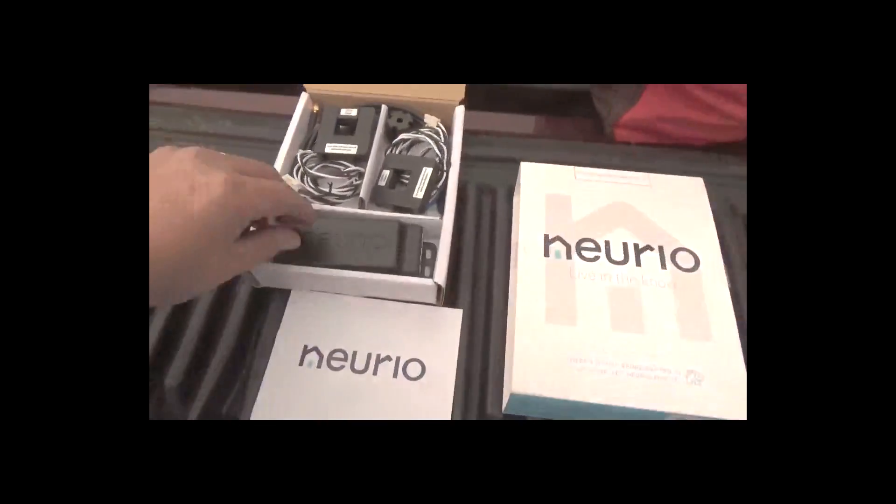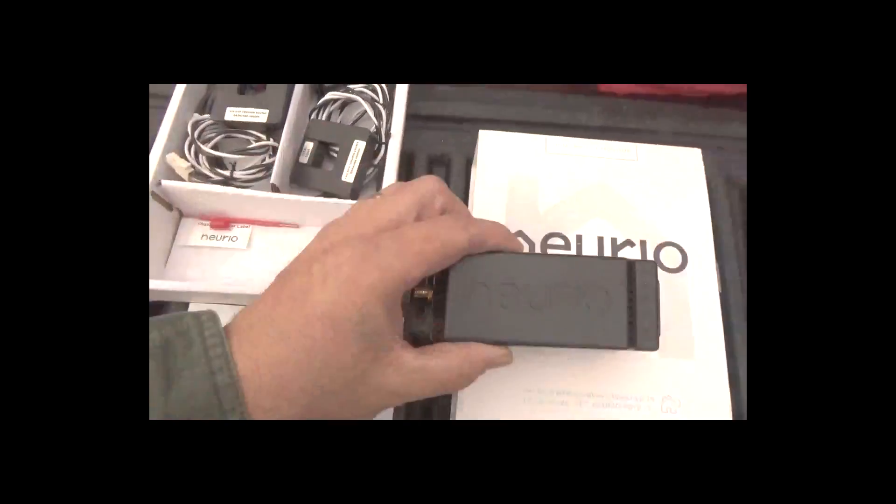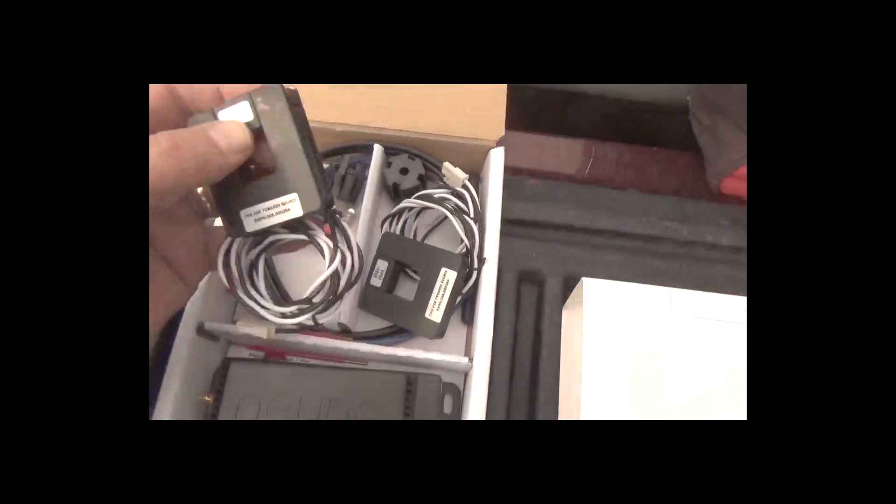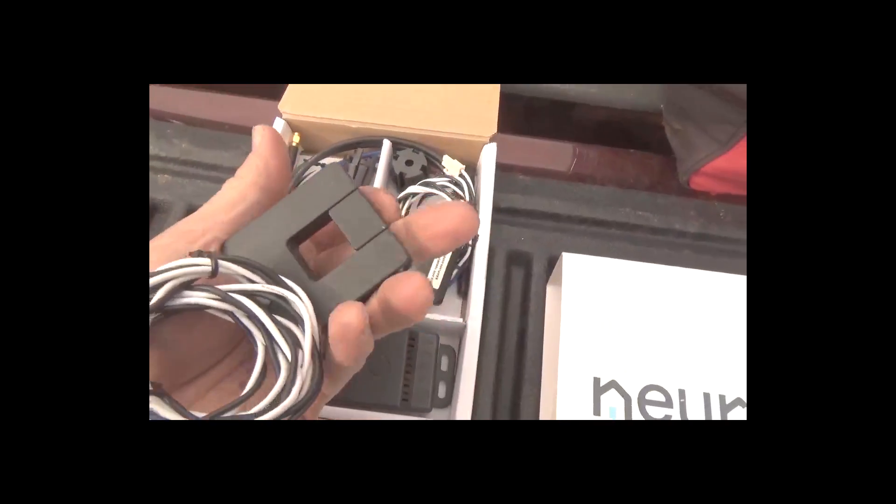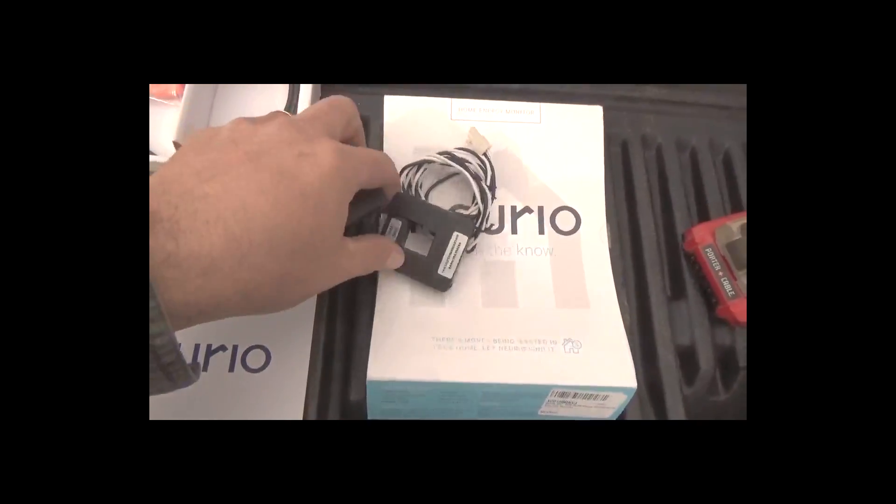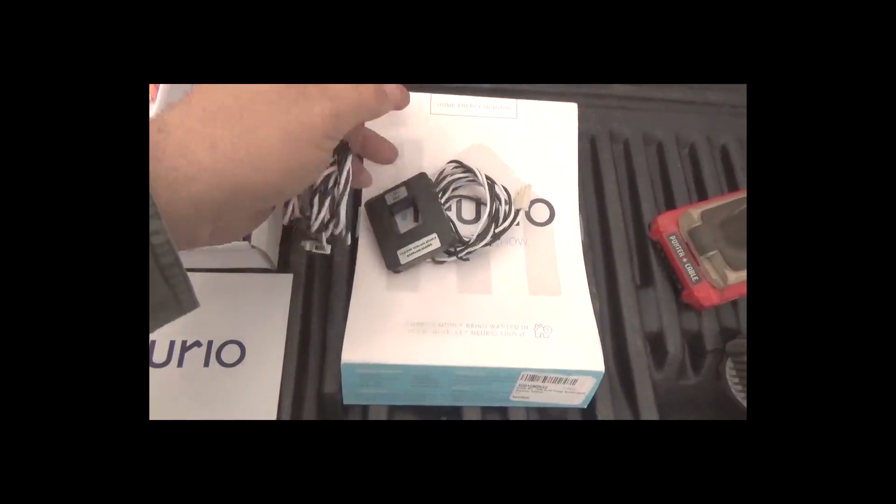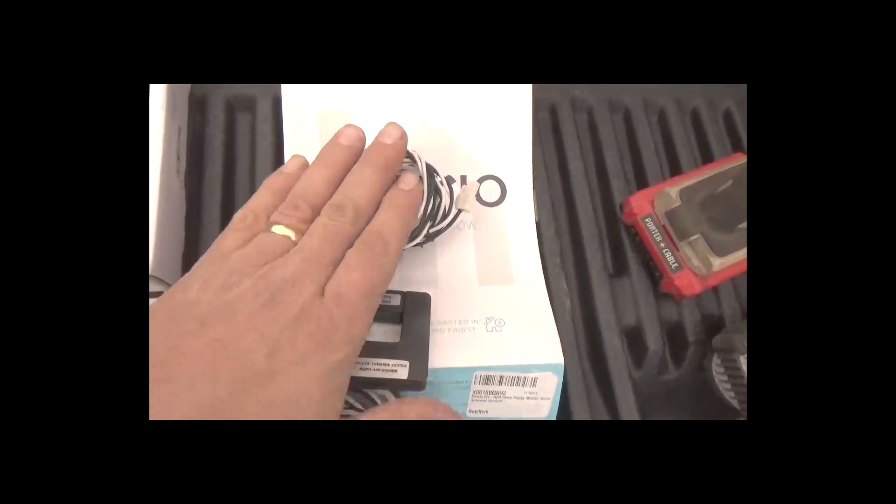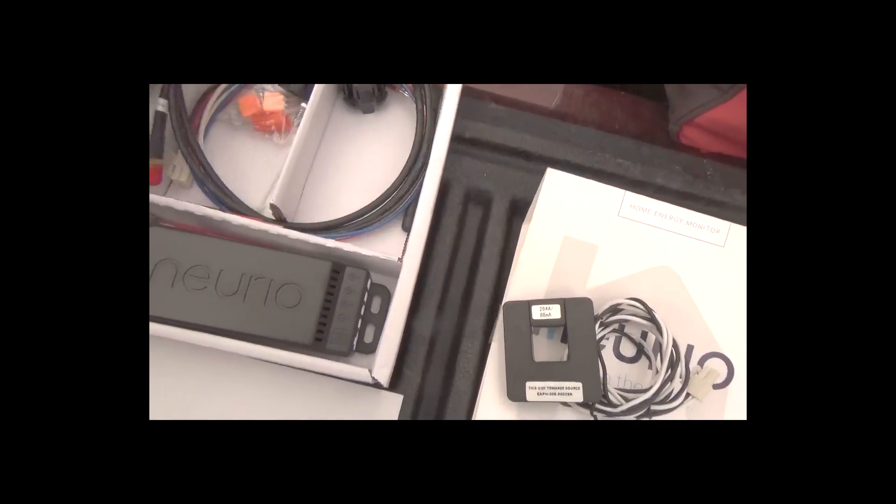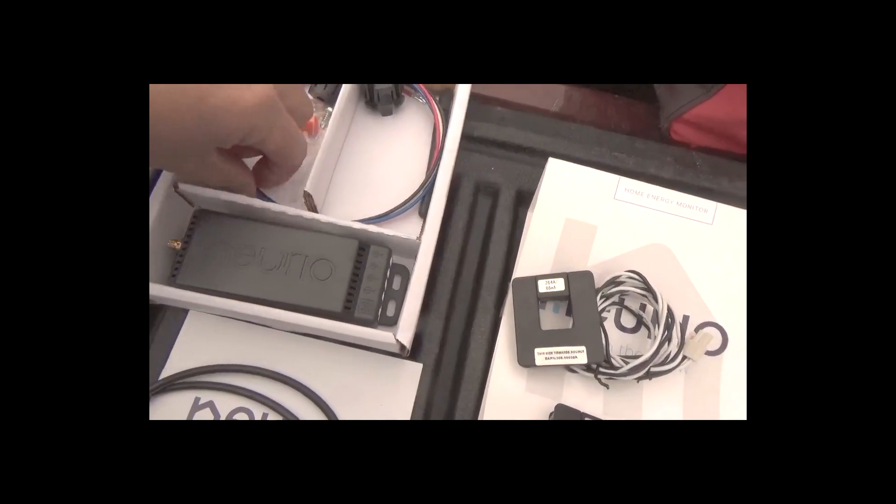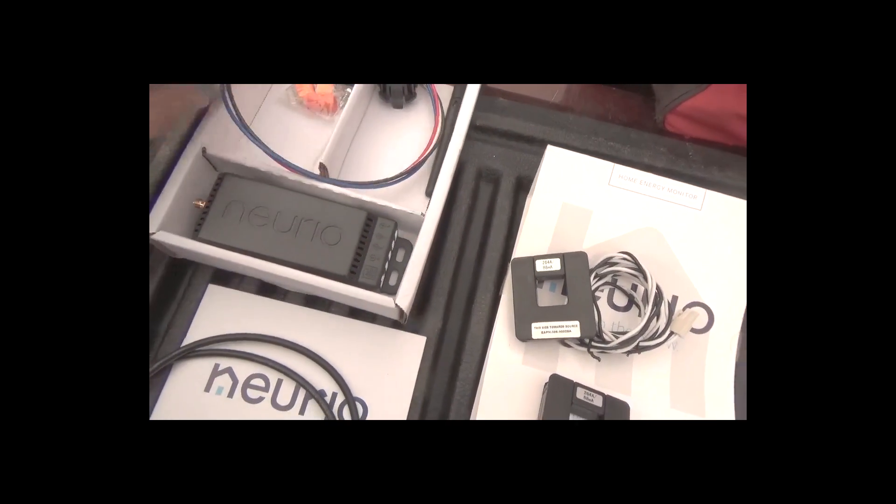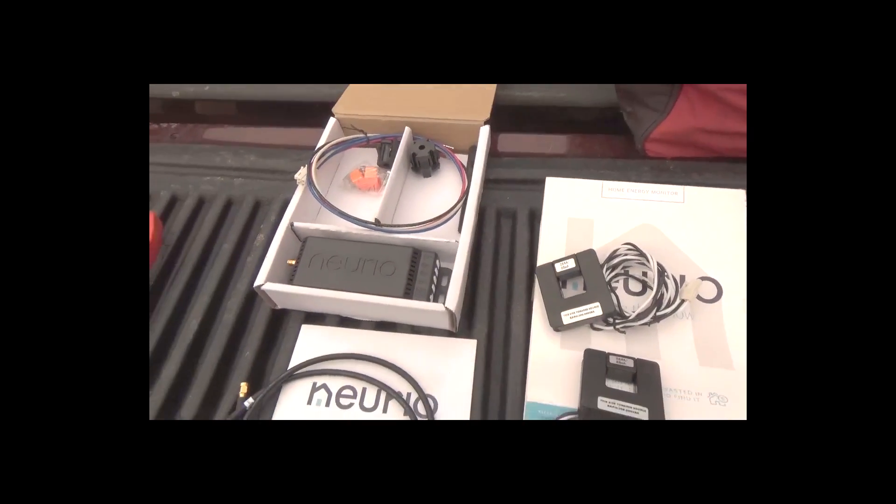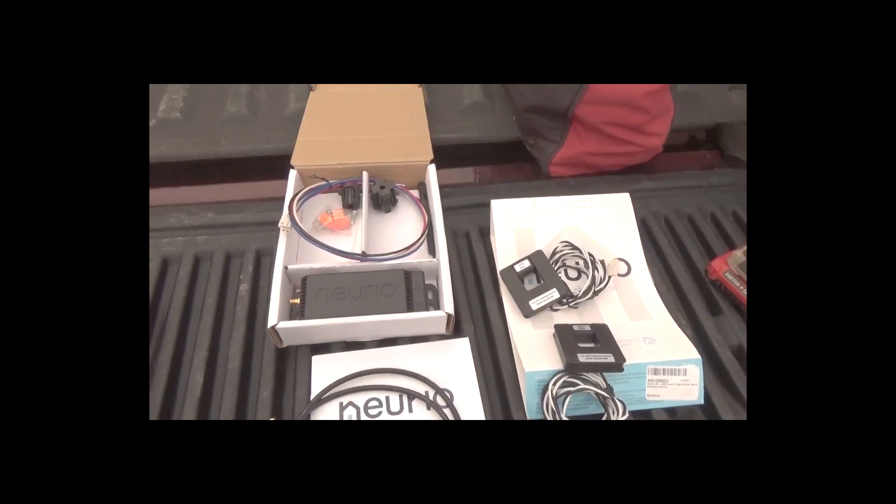There's a unit I'm going to put inside the power panel, the Neurio unit. There are CTs, current transformers, that will get put around the leads and they're directional, and they will be used to calculate. So we'll have amperage going through there and we'll have voltage. I put in two breakers in the panel, two 15 amp breakers, and we'll connect them up to the Neurio.